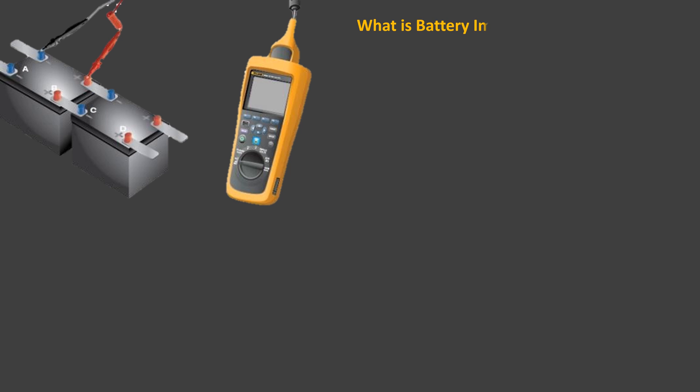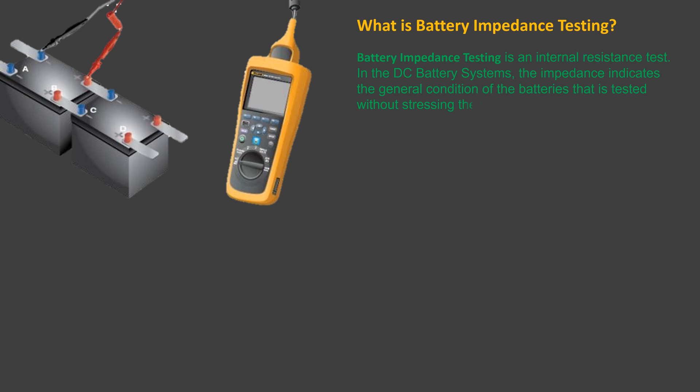What is battery impedance testing? Battery impedance testing is an internal resistance test. In the DC battery system, the impedance indicates the general condition of the batteries that is tested without stressing the whole system and the batteries themselves, because it tests the whole system between two terminal plates of the battery. It is ideal for spotting any weakness in cells.